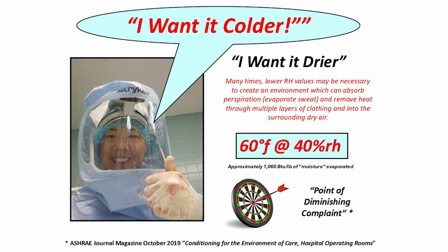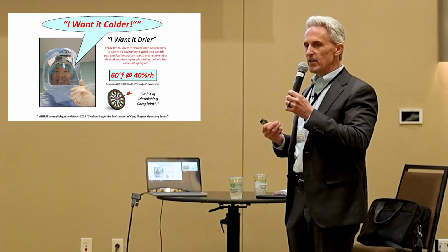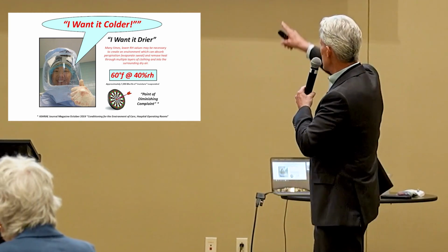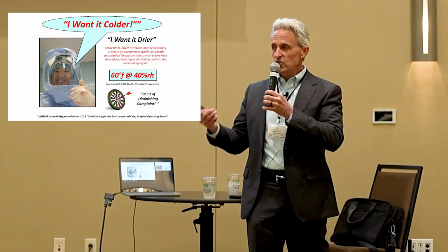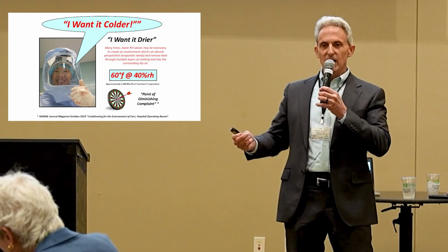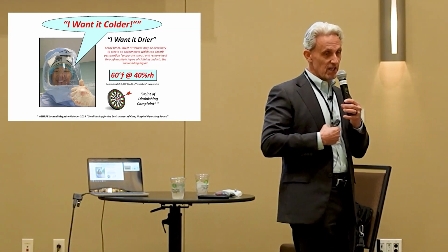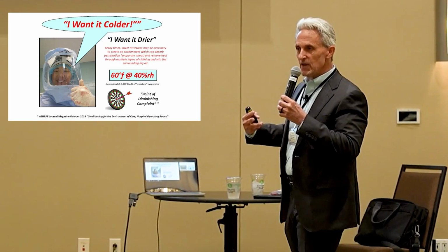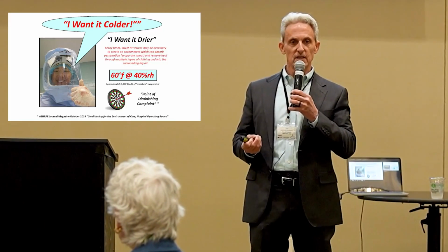But what they don't understand is what they really want is for the environment to be drier. Yes, cold is important. They do want it cold. In fact, they usually want it somewhere around 60 degrees Fahrenheit. But they also need it dry, and here's why. We need to encapsulate them in an environment of air that is dry enough to be able to wick the moisture from their skin through 2 or 3 layers of clothing into the air that surrounds them, to evaporate that moisture from their skin and to evaporatively cool their bodies.